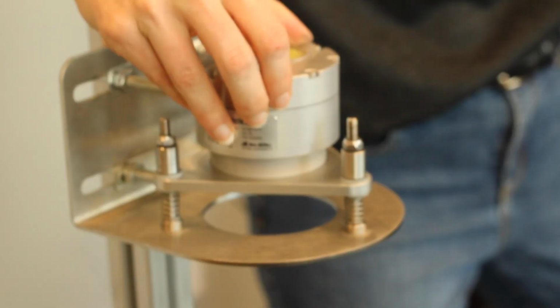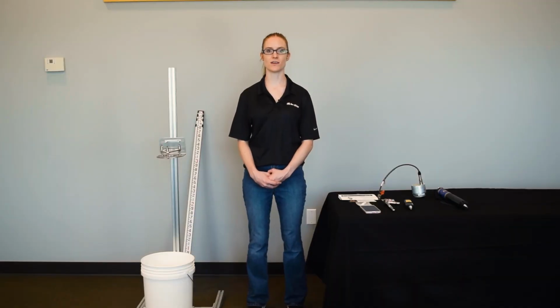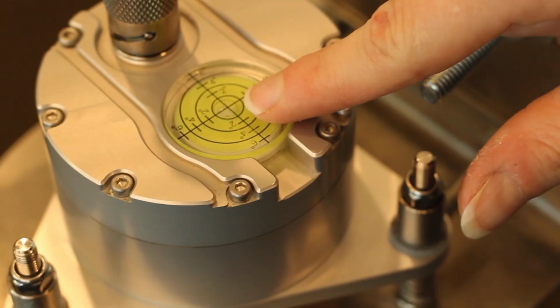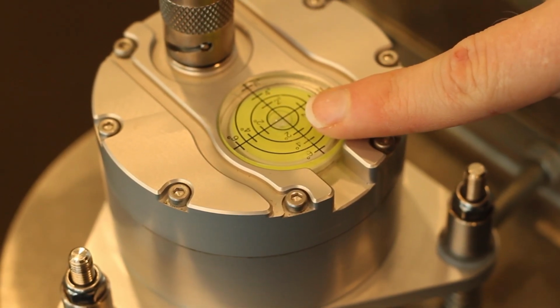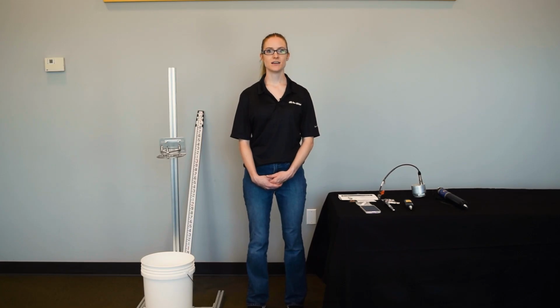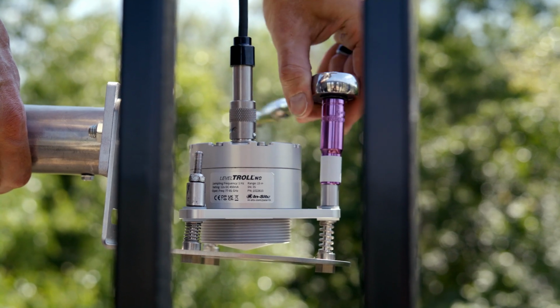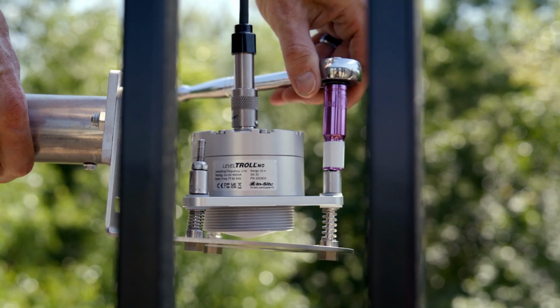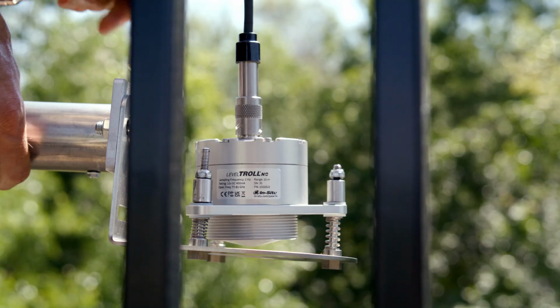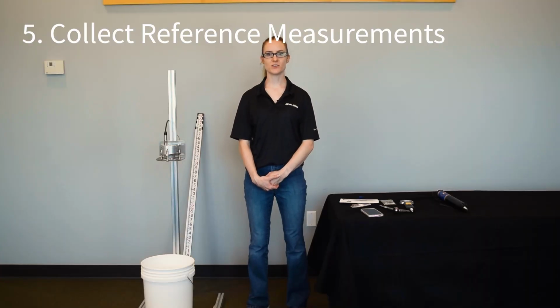You don't need to reinstall the nut if you're using the mounting bracket, but it's available if you're using a mounting system without threads. If you look over the top of the instrument, you'll see a yellow bubble level, which can help you view the sensor tilt. Use a socket wrench with a 10mm deep socket to adjust the 3 leveling bolts until the instrument is level. Now that your instrument is level in its final deployment location, you can collect measurements from the site.